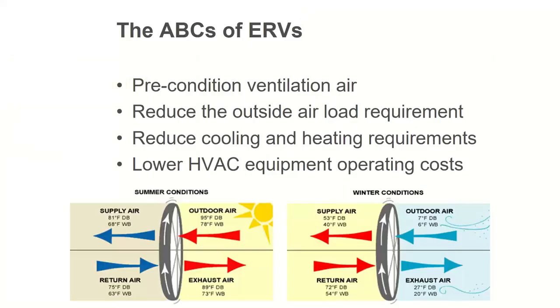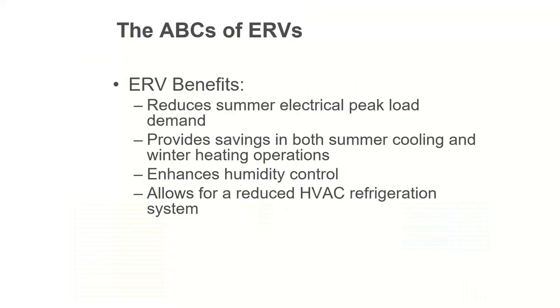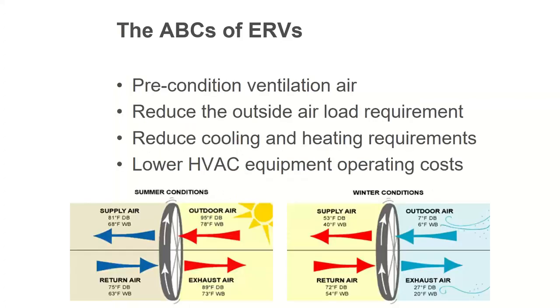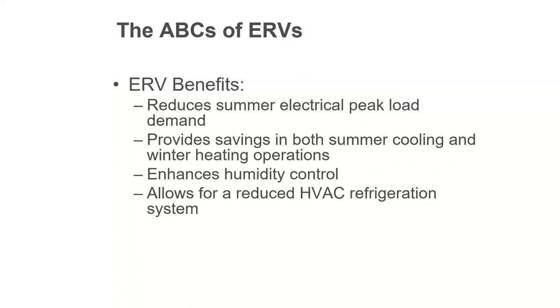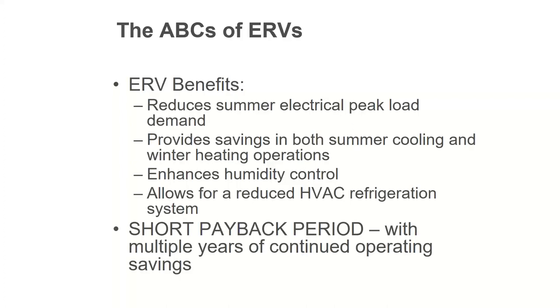It's hokey, I get it, but we do a lot of them that way. In fact, we almost do all of them that way now, unless somebody's stubborn. Benefits of the ERV: better dehumidification control, better humidification control, right? I was getting free humidity in the winter, free dehumidification in the summer, reduced peak loads, reduced energy consumption, buy a smaller chiller, buy a smaller condensing unit, buy a smaller gas heater, buy a smaller boiler. It's taking care of a lot of stuff for me.